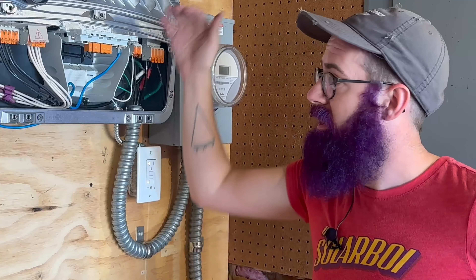On the DC side here, I wanted to explain a little bit about what's going on over here. We have two what is called maximum power point trackers. Fronius's tech behind tracking the maximum power point of your panels is called the Dynamic Peak Manager. Now, this system is not complicated. It is a solar array that does not get shaded. All of the strings are exactly the same length, but I am putting 2 strings each on the 2 maximum power point trackers, and they will get adjusted independently of each other.